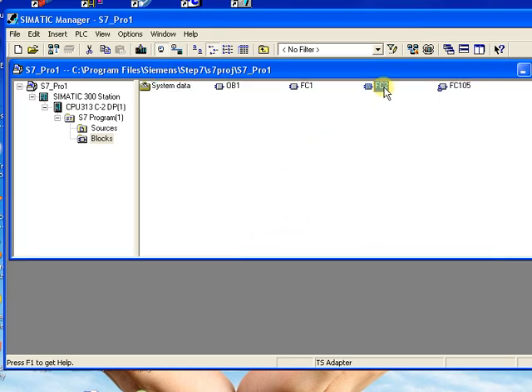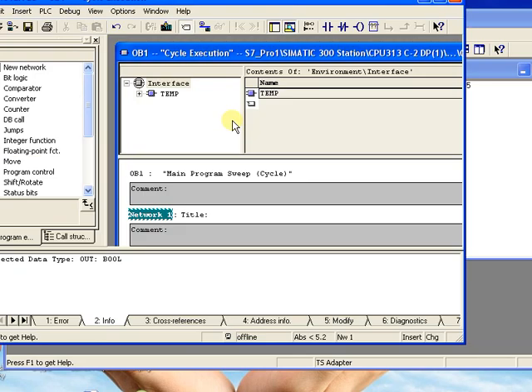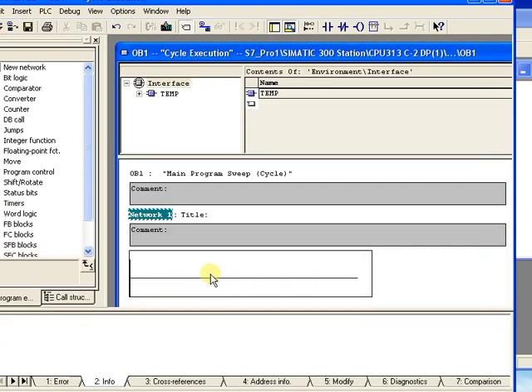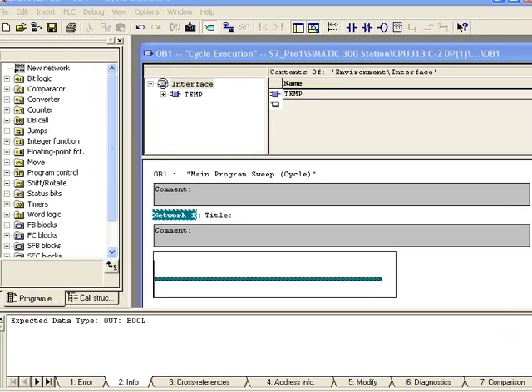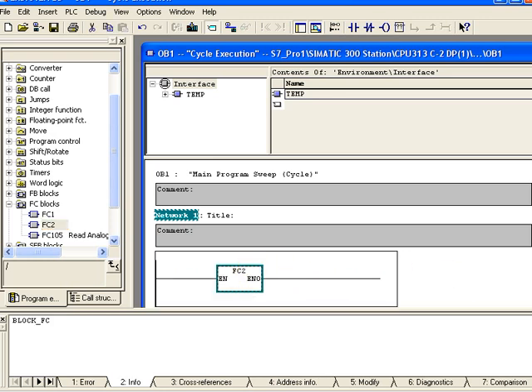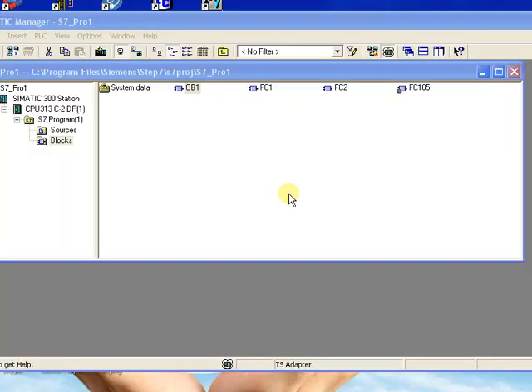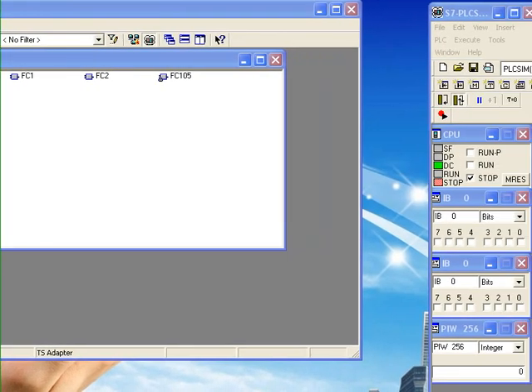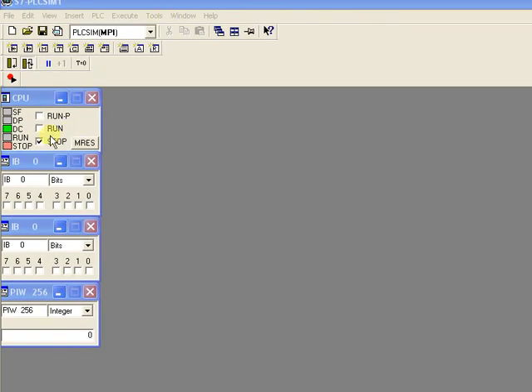Now our FC2 function is added. Double click the OB block — I need to add the function block inside the OB block because OB1 is the cycle execution block. Click the plus button and you will see all the function blocks. Drag and drop the function block inside the OB block. The function block is now added inside the OB block. Now click the Simulation button to start the simulation. In the simulation screen you see the CPU, the Stop button, and the Run button. If you click Run, the CPU runs; if you click Stop, the CPU stops. You can also see the input module, output module, and the analog module.